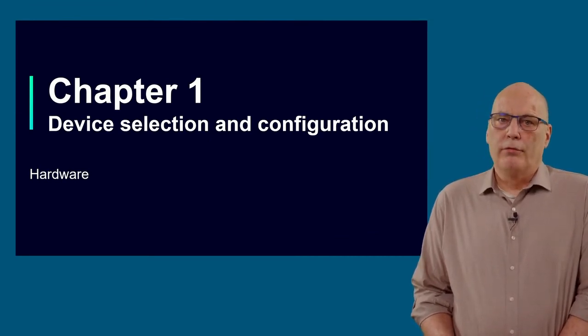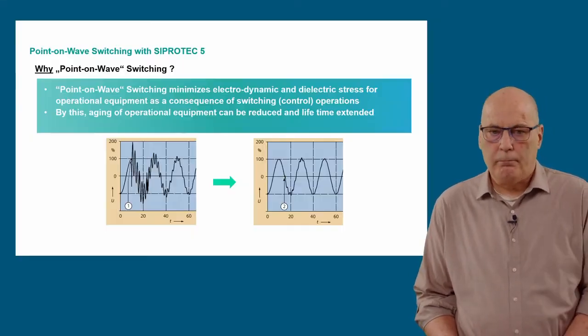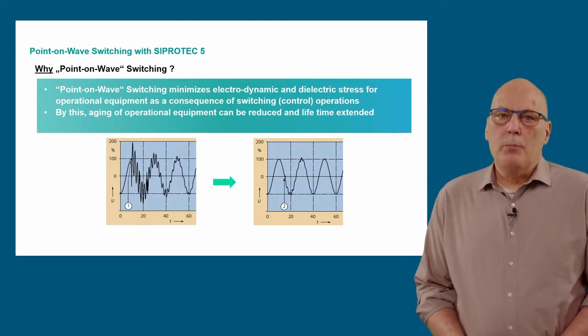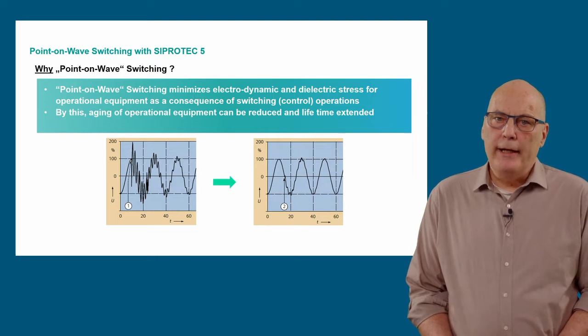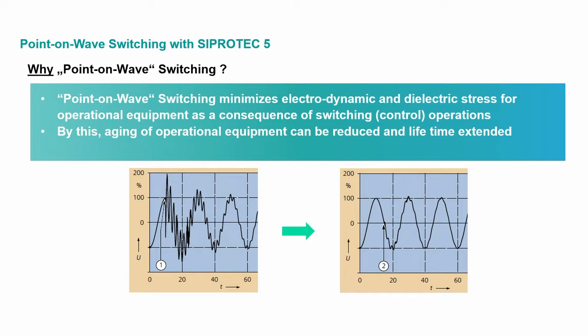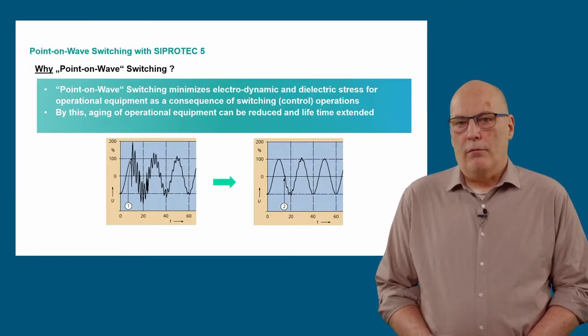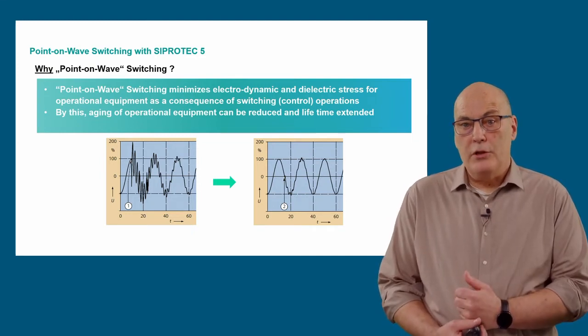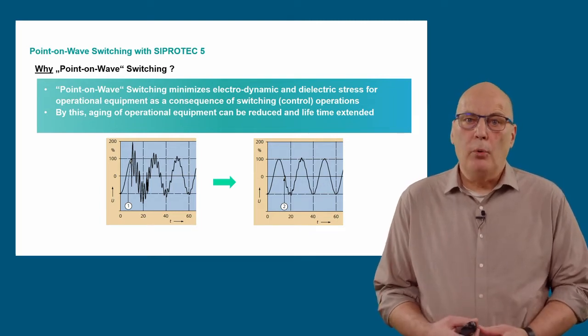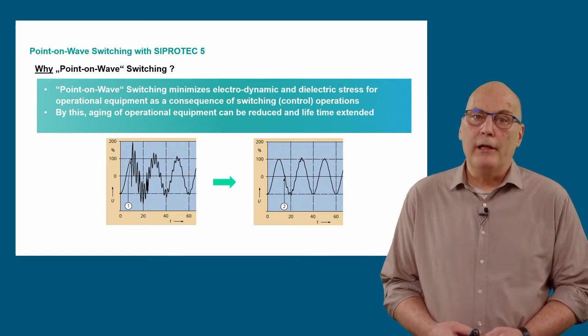Starting with Chapter 1: device selection, configuration, and hardware requirements. Where is point-on-wave switching a benefit? A capacitive load or cap bank was energized. On the left side, the instant of closing was at voltage peak and severe voltage transients are seen. These transients have the potential to severely damage plant and equipment, including the energized capacitor. On the right-hand side, the same capacitor was energized correctly with point-on-wave switching, close to the zero crossing of the voltage, resulting in almost no induced transients.